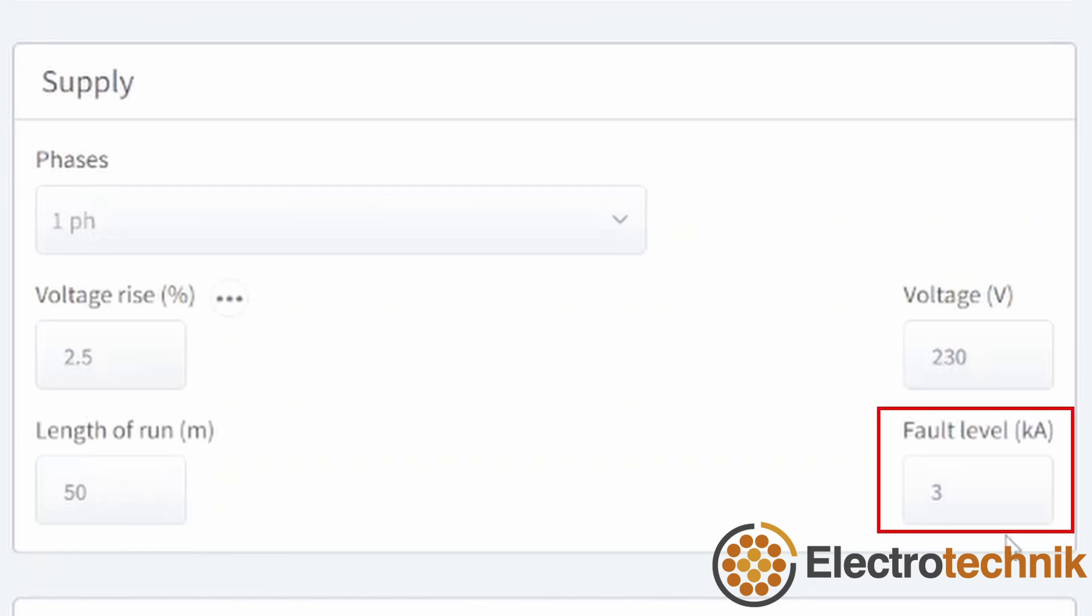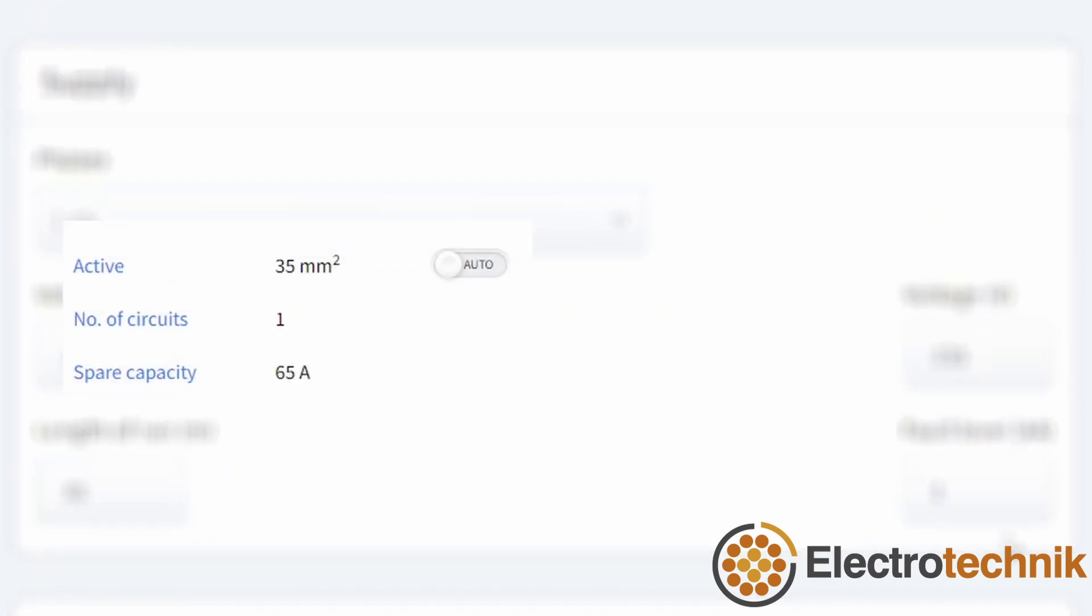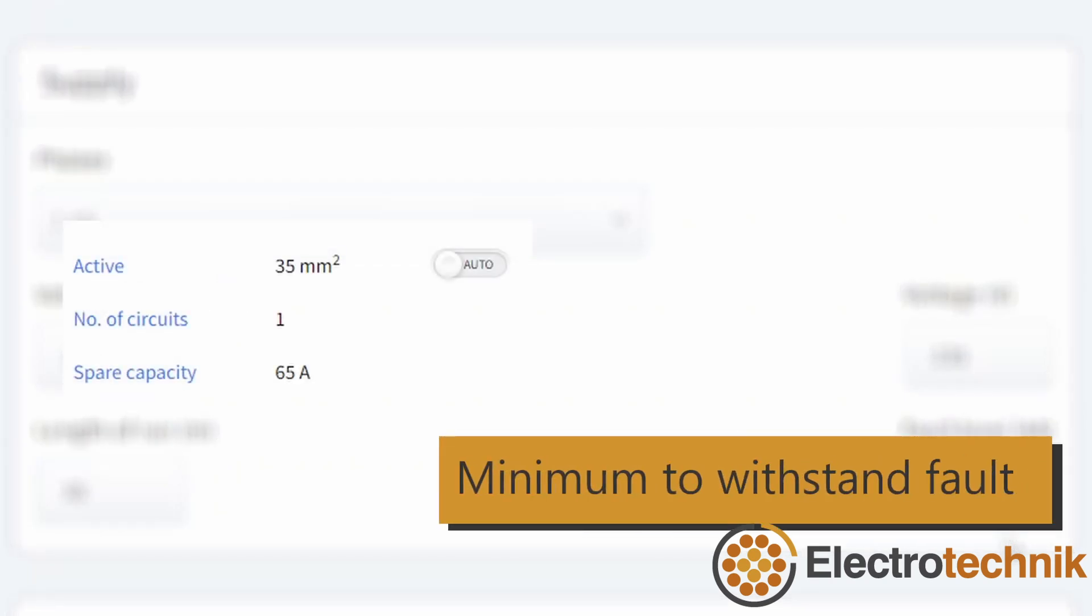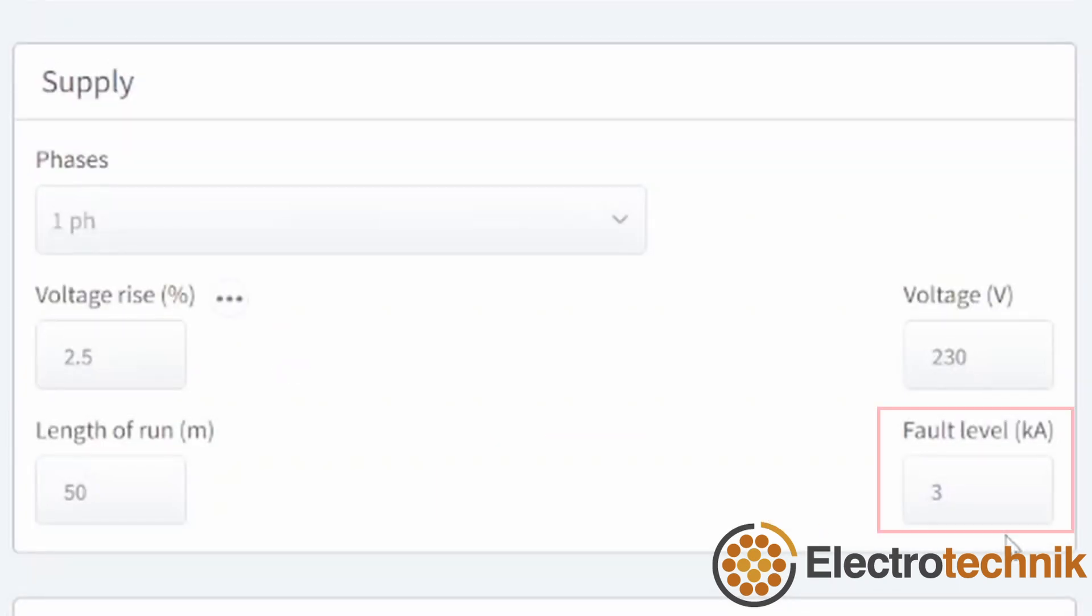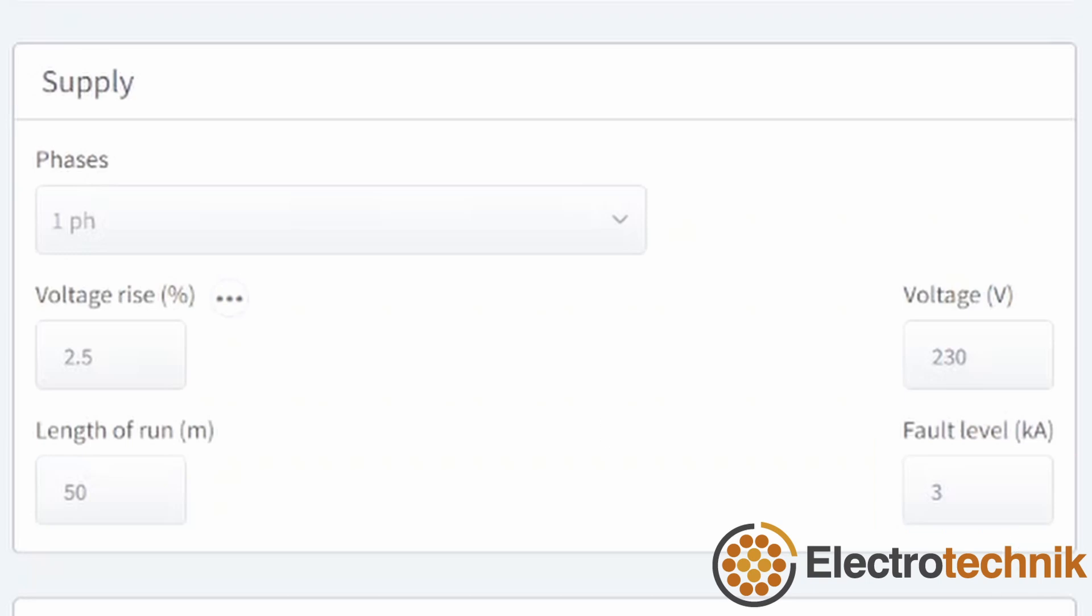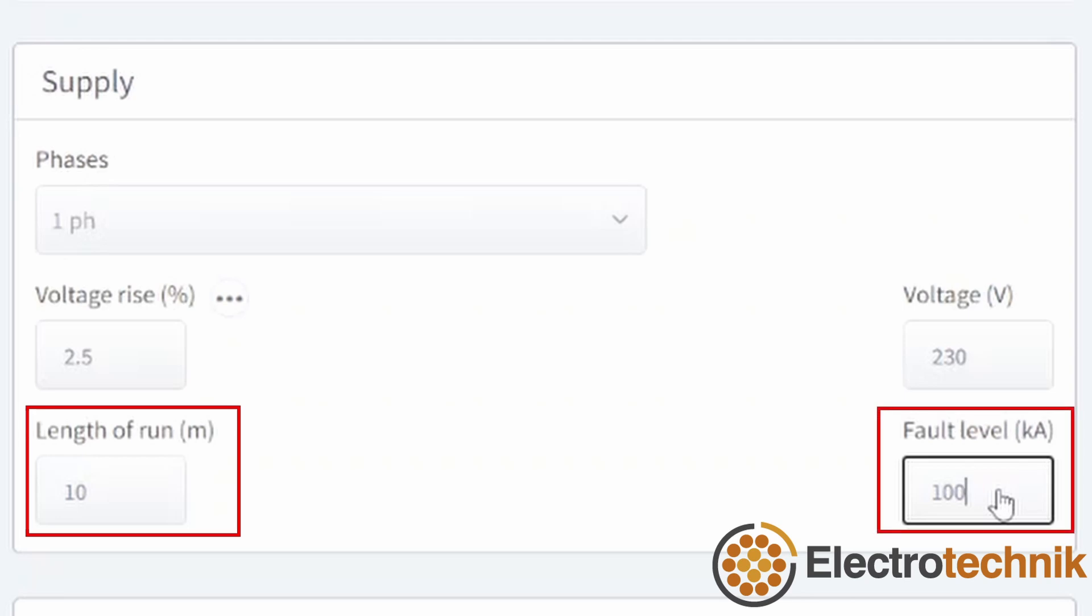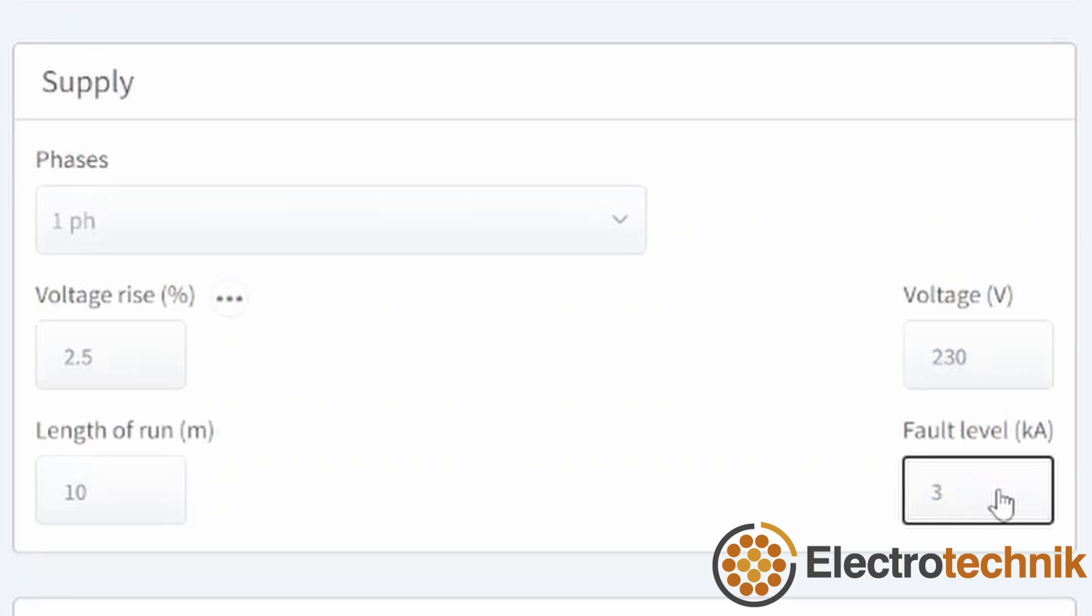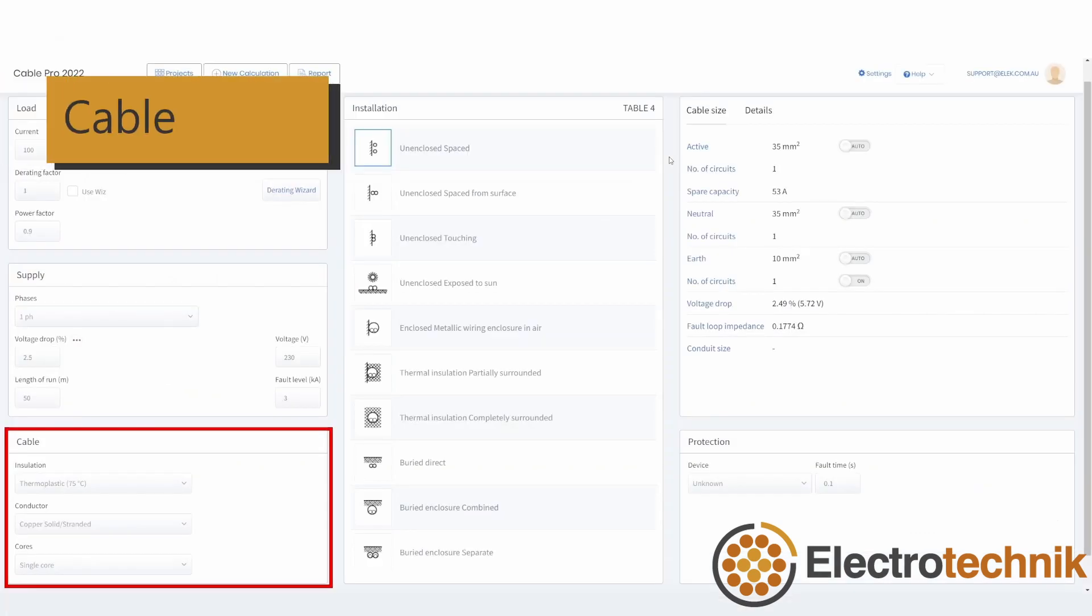Fault level is the prospective fault current level at the point of supply of the cable which affects the short circuit rating of the cable. The resultant cable size is the minimum size to withstand the fault current. Note that it is meant to be the actual fault level for the installation and not the rated breaking capacity of the circuit breaker. It can be quite difficult to get an accurate value for fault level but it should be provided by the power authority. Sometimes confusing results are seen for very small cable sizes when the length of run is short and the fault level is overly high. In these cases, the fault level can be the dictating factor for minimum cable size. To check, just reduce the fault level.